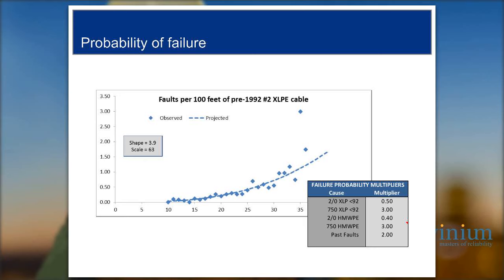Many utilities don't have this kind of data — their system isn't large enough or they haven't tracked it well enough to do a curve fit. They can try to share data with other utilities, find industry information, or — very commonly — rely on a combination of subject matter expertise and available data to calibrate a failure probability curve that projects the right total number of failures. A very detailed, rigorous database is not required to get started. You can almost always make do with whatever you have, even if all you have is the opinion of the subject matter experts at your utility.